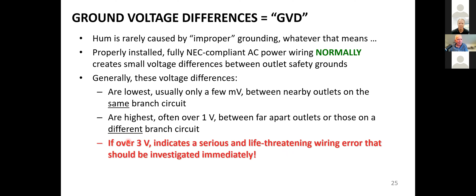But the bottom line here is that a properly installed, fully compliant AC power wiring normally creates these small voltage differences. Now, if you ever see a voltage over 3 volts, I won't explain why that is, but it's the maximum voltage you should ever see between ground and neutral at an outlet. It has to do with voltage drops under full load. They're allowed to be 3 volts on each trip back to the ground on the panel under full load. That's a recommendation by code. So the total voltage drop would be 6 volts, which is 5% regulation at a 120 volt outlet, or would cause a 5% drop in voltage. So half of that would appear between neutral and the ground. So that's why it's the maximum.